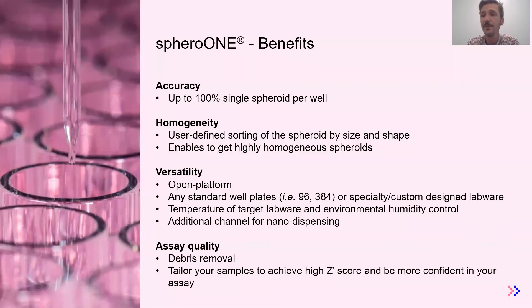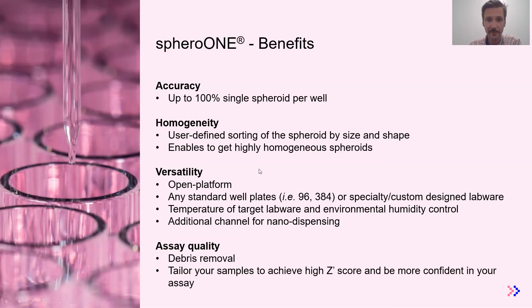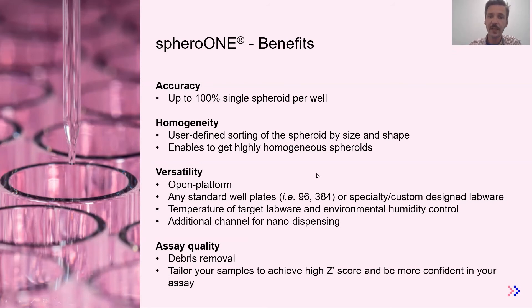What are the benefits of the SpheroONE? Accuracy: up to 100% single sphere dispense in each well of your target well plate. Because the user can define isolation parameters, we can isolate very homogeneous populations from an originally heterogeneous population. The SpheroONE is an open platform compatible with any standard labware—96 or 384 well plates—as well as specialized and custom labware such as lab-on-chip devices. The target labware is temperature controlled and the environmental chamber is humidity controlled. There is a possibility to add a second dispensing channel for bulk media or reagent dispensing. Because the suspension aspirated by SpheroONE can be strained, assay plates come out very clean, free of any debris.